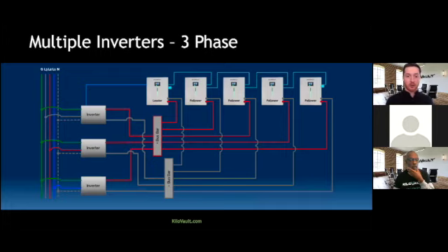All right, so moving right along, we just wanted to show a brief diagram of a larger installation here. We have a 5-stack of batteries all going to their common buses. And this is being used in a 3-phase inverter setup. Ultimately, the batteries don't really care. They're just looking at the DC side of the inverter. Here we do have a representation of closed loop communication. You'll see in the top left, we have a comm cable between our leader battery and our leader inverter. This is a good example of how these batteries might be used in a light commercial application.